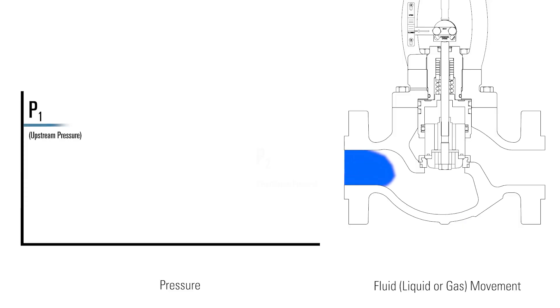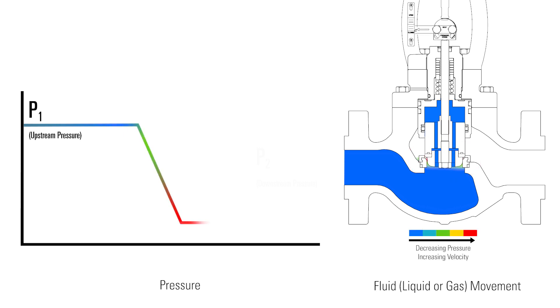Fluid enters a valve at its upstream pressure, shown here as P1. As it continues through the valve and encounters the trim, the fluid reaches its greatest restriction. Immediately after this point, the fluid drops to its lowest pressure inside the valve, also referred to as the vena contracta.